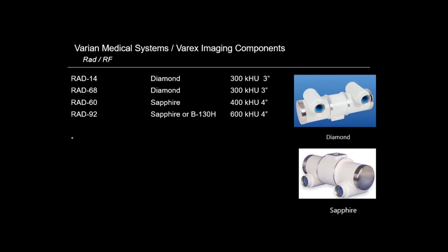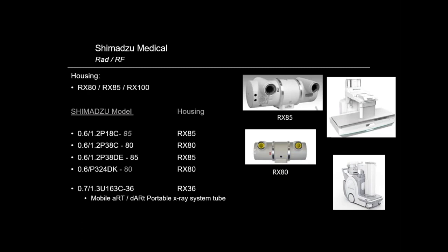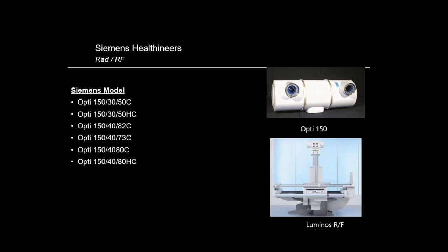Varian medical systems or Varex. These are very common diagnostic tubes, somewhat generic in their housings. You'll find these on a lot of systems. Shimadzu, more and more Shimadzu systems in the marketplace. The RadSpeed or the portable. Siemens are almost all 600 KHU, and they all use this Opti 100, 150 housing for diagnostic tubes. They have cath lab tubes that are different, but for most of the diagnostic tubes, they're using an Opti 150, or they refer to it as an Opti, it's really the same.